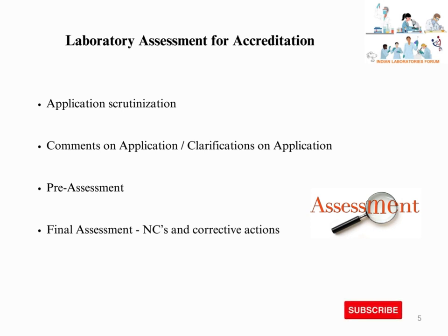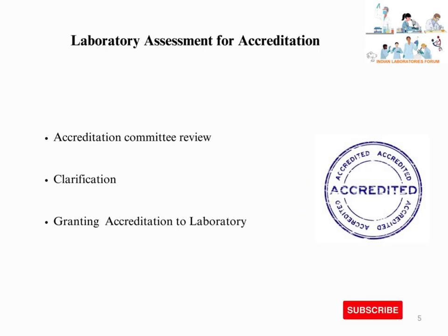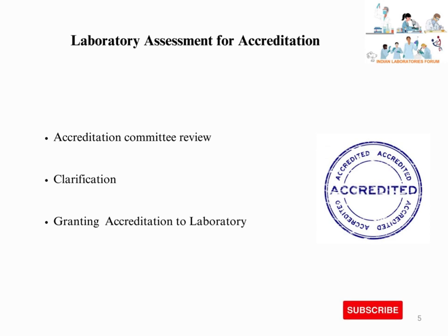Assigned auditors complete the final assessment and raise non-conformances if required. The laboratory takes proper corrective actions and submits documentary evidence to the auditors for review and closure. If corrective actions are satisfactory, auditors close the non-conformances. All non-conformances and corrective actions are then reviewed by expert members of the accreditation committee or accreditation task force. If any clarification is required, the accreditation body communicates this to the laboratory. Upon satisfactory clarifications, the committee grants accreditation to the laboratory.